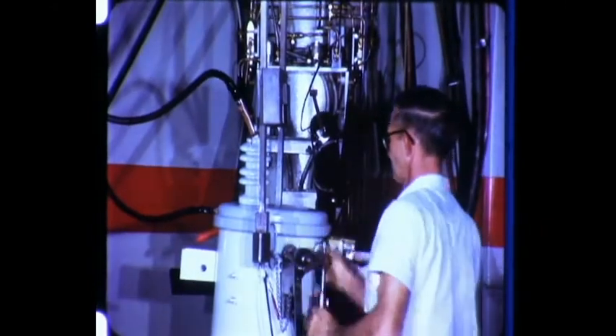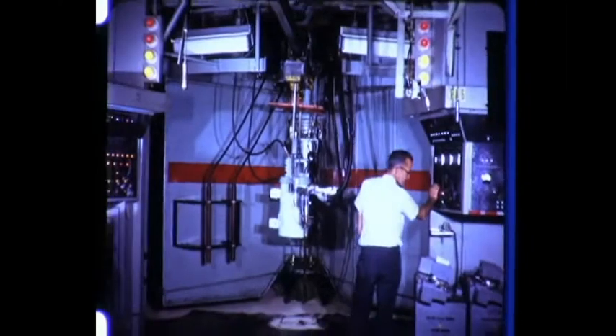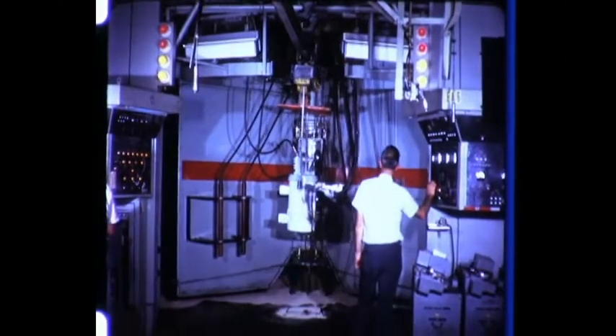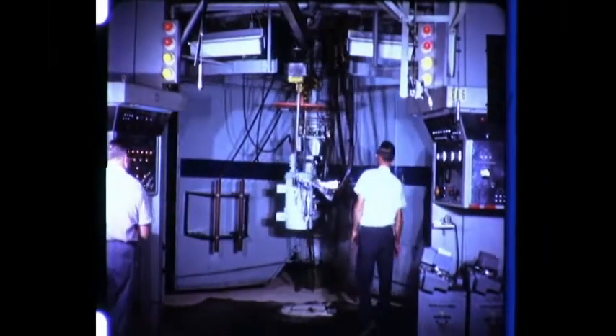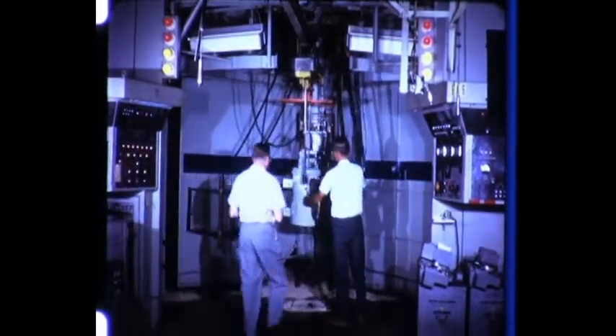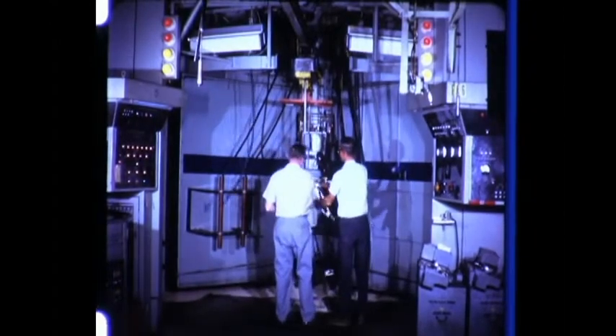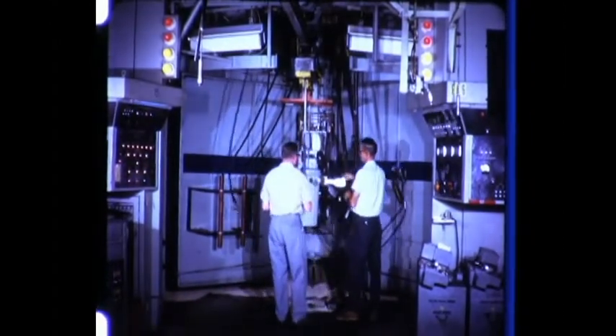Electrical checks, such as the automatic carousel test for transformers, assure design performance. Ratio, polarity, losses, impedance, circuit breaker operation, all are verified. High voltage tests at impulse and power frequencies assure integrity of the complete insulation system. This flashover test, occurring at the rate of 200,000 cycles per second, at voltages well above levels the insulator sees in normal service, seeks out imperfections before shipping.